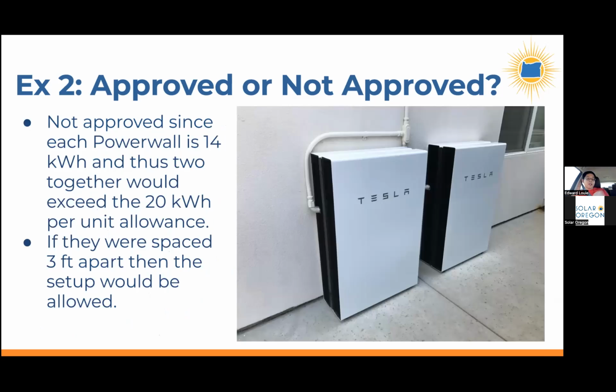Okay, well, here's another example. This is a configuration you see quite often: 2 Tesla Powerwalls put right next to each other side by side. So this again will not be allowed in the new requirements, because each of them is 14 kilowatt hours. You put 2 right next to each other, that exceeds the 20 kilowatt hour per unit allowance. And so the requirement now is that you need to space these Tesla Powerwalls 3 feet apart. Then it would be allowed.